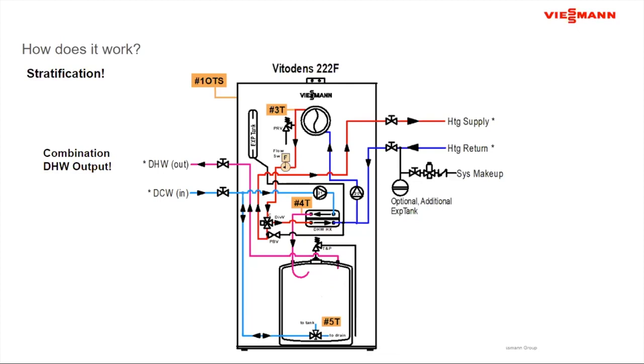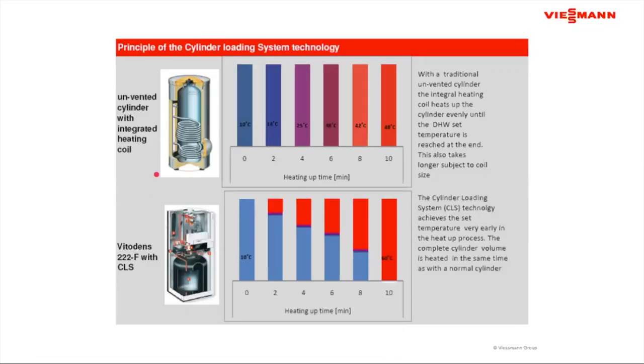60 gallons of domestic hot water in 10 minutes because of this combined performance. Okay. And what it does is it gives me hot water faster than doing a conventional tank. Because on the conventional tank size, when I start to heat the water up, it's not that I heat only a segment of the water up to temperature. I actually set up a convection current in here, and then the entire tank heats up together. So if I start with a cold tank, over a 10-minute period, the temperature of the tank increases fairly consistently throughout the tank.